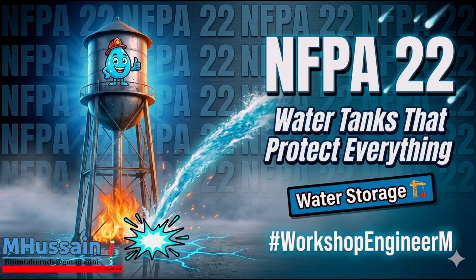Yes, and this is where understanding fluid mechanics meets fire dynamics. You build this highly insulated vertical tube specifically to keep the cold air out. But if a fire starts at the base of the tower, that vertical insulated tube will act exactly like a chimney. The heat will enter the bottom, and convective drafts will pull that superheated air straight up the pipe casing, accelerating the fire, melting the insulation, and potentially boiling the water inside the discharge pipe, or destroying the tank connections 100 feet in the air. The fire stops plug the cavity, breaking the chimney effect. You are designing against the cold, but the code forces you to remember that the primary overriding threat is always fire.